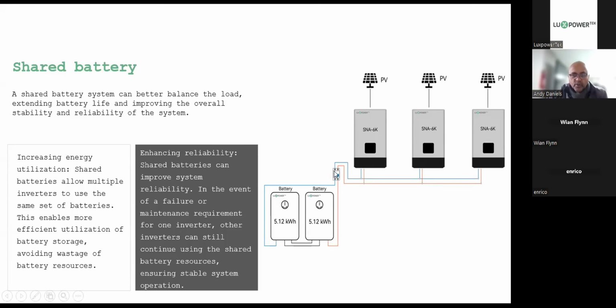The bus bar is not drawn on here, but ideally all the inverters will have access to the battery bank. And the reason we recommend this is that a shared battery bank can better balance the load and it extends the life of the battery, improving the overall stability and reliability of the battery. Because remember, imagine you had one battery on each one of these.